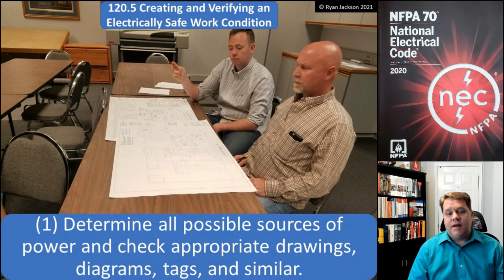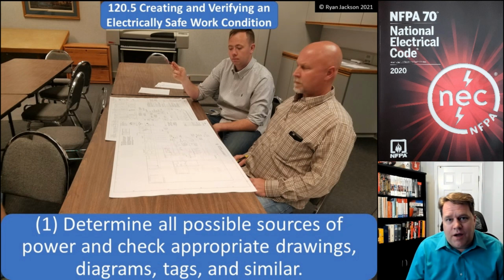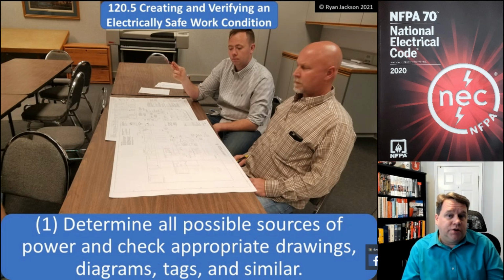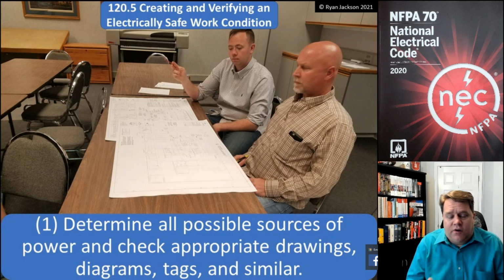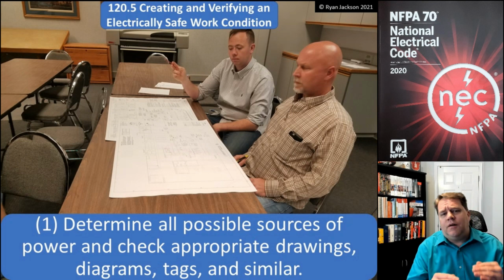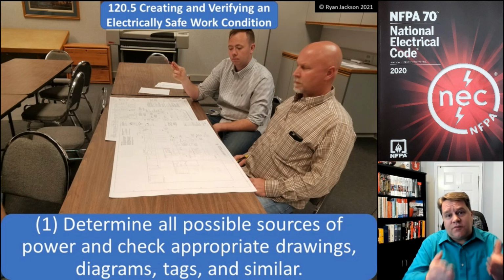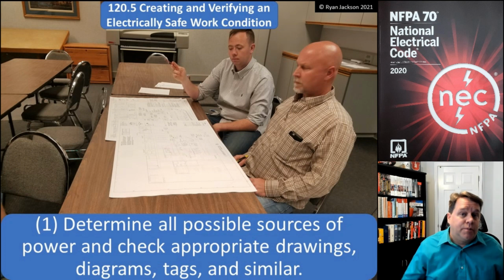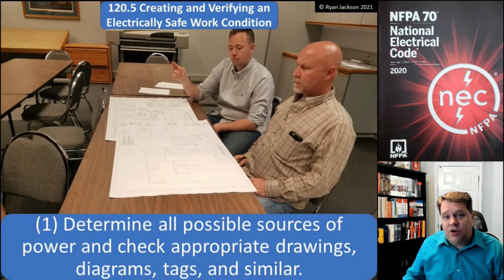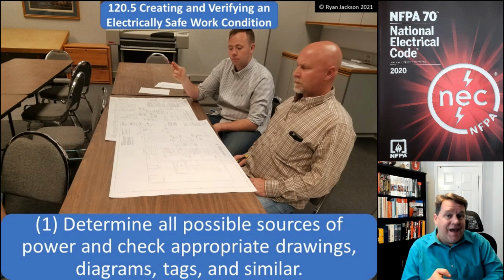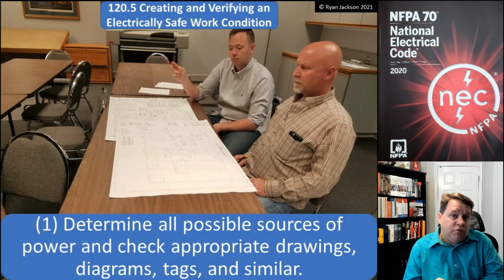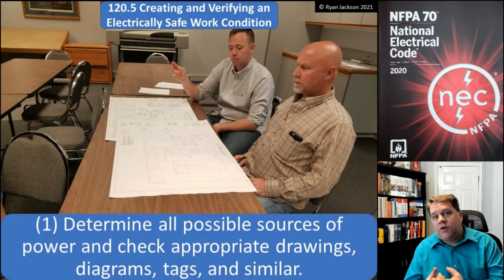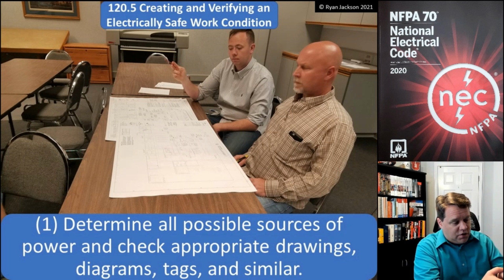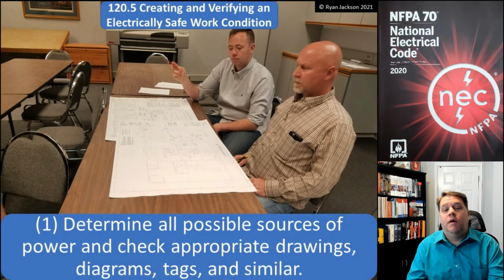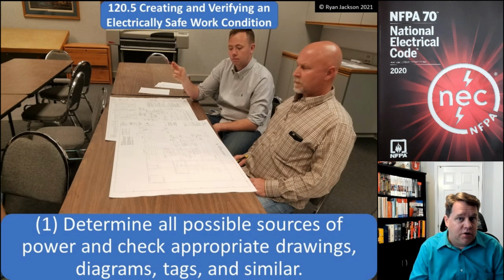Now, this may seem like a no-brainer. I mean, look, if you've got a simple commercial building, this might be a very simple part of the procedure. But as you get into more and more complex systems, this might be the most difficult part of the entire process, determining what you need to shut off. You might have to shut off the power circuit and the control circuit. Or if you're in a really complex installation, you might have to look at anything that could possibly energize it. The regular source, the backup source like a generator, maybe there is a UPS system. There could be a lot of different voltage sources that you need to shut off.